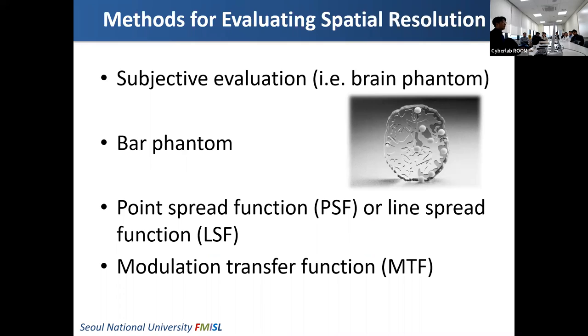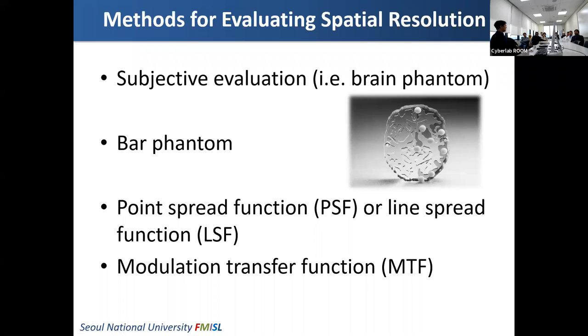Let me tell you about the methods for evaluating spatial resolution — how we can measure it. The easiest way would be subjective evaluation. If we read the image, we know whether it has good spatial resolution or not. For example, if we scan the same brain phantoms, we can subjectively assess how good the spatial resolution of our system is. Sometimes we use a specialized bar phantom with several bars of different spacing to assess spatial resolution.